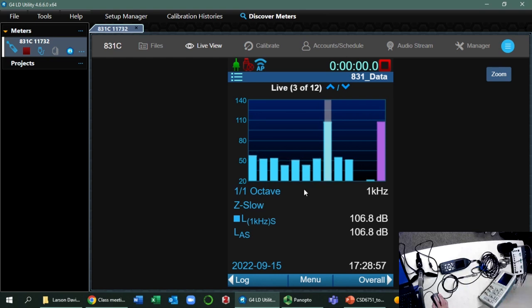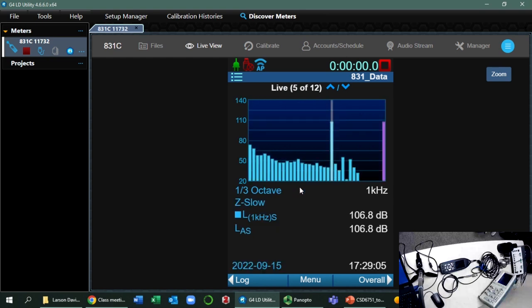For page 3, it's 1 octave band. The width of each bar is 1 octave band. But for page 5, the width is only 1/3 of an octave band. So obviously the resolution is better. So we will use 1/3 octave band. It's almost an industrial standard when you calibrate pure tones or an audiometer or do standard calibration. Whenever you need frequency specific information, you use 1/3 octave band. Okay.